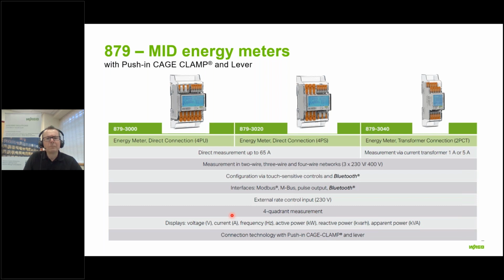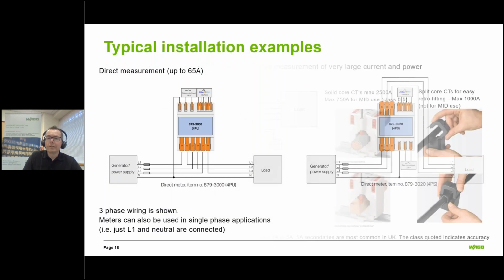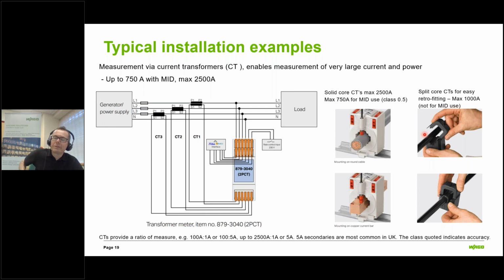Can the 879 clamps be used for three-phase motors that cannot be turned off? They're looking at between 5 and 16 amp per phase. Effectively, if you're looking at this type of CT, then providing it's safe to work, sometimes there is quite strict legislation around working on equipment that's operational. I've been involved in the past in what they call safe systems of work and permits to work. So providing those requirements are met, then in principle these can be snapped over a cable. The health and safety and safe systems of work should be observed if that's going to be undertaken, but it doesn't disturb the existing cable.